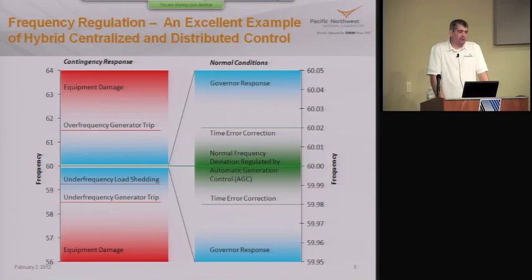So the analogy is like throwing a sandbag off your hot air balloon, right? You need to get rid of that weight to reach equilibrium. The idea here is that if you're in low frequency, you shed load to recover back to nominal. These are all automated controls that I talked about. There's no human in the loop on any of these decisions. And some of them happen very fast. Underfrequency load shedding can be triggered on very, very fast timescales.